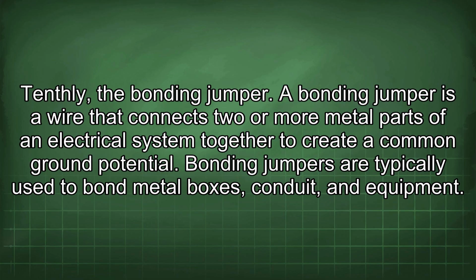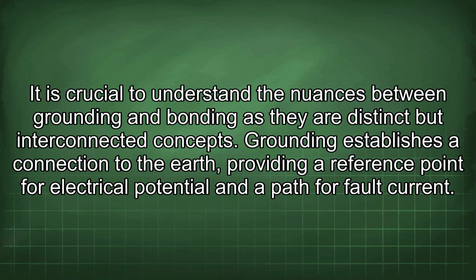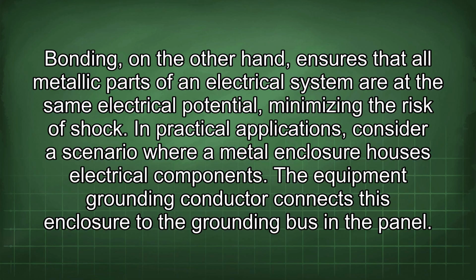A bonding jumper is a wire that connects two or more metal parts of an electrical system together to create a common ground potential. Bonding jumpers are typically used to bond metal boxes, conduit, and equipment. It is crucial to understand the nuances between grounding and bonding as they are distinct but interconnected concepts. Grounding establishes a connection to the earth, providing a reference point for electrical potential and a path for fault current. Bonding, on the other hand, ensures that all metallic parts of an electrical system are at the same electrical potential, minimizing the risk of shock.